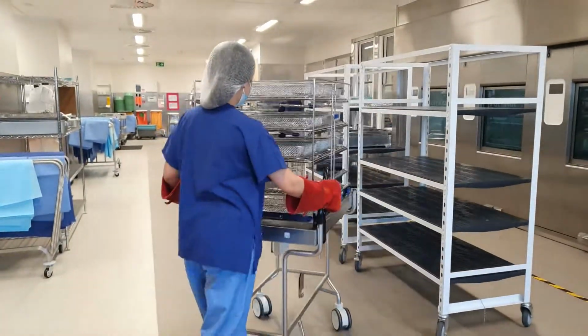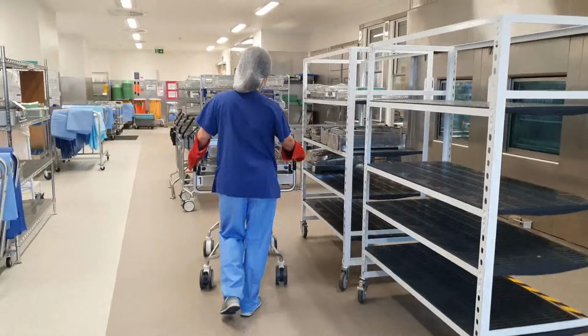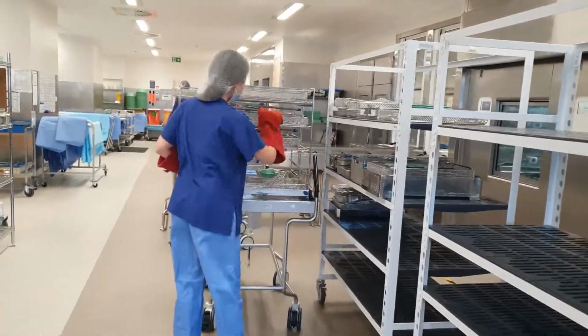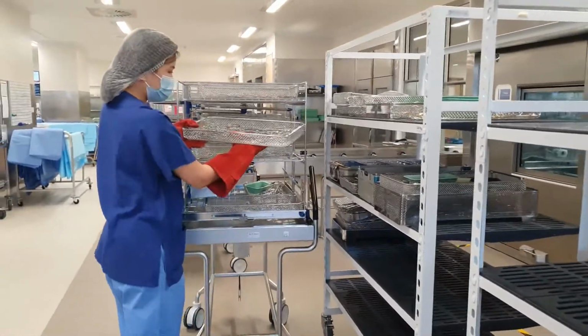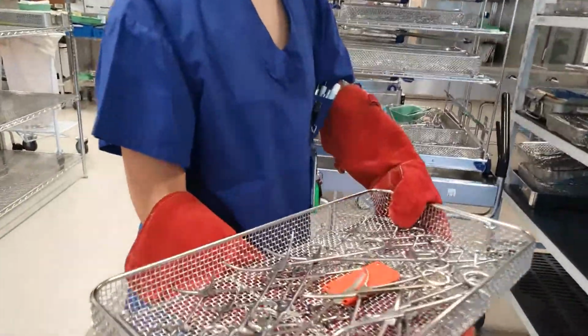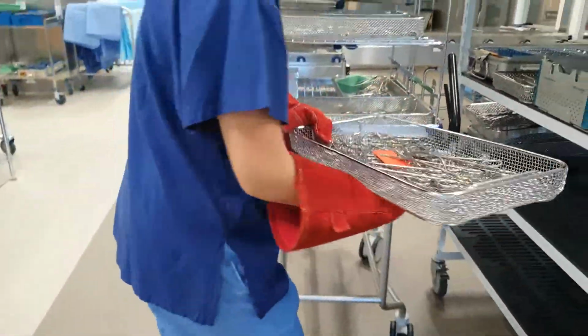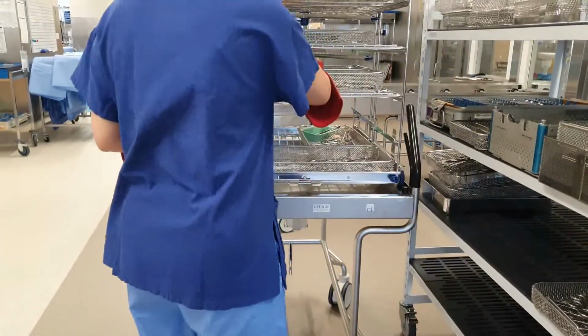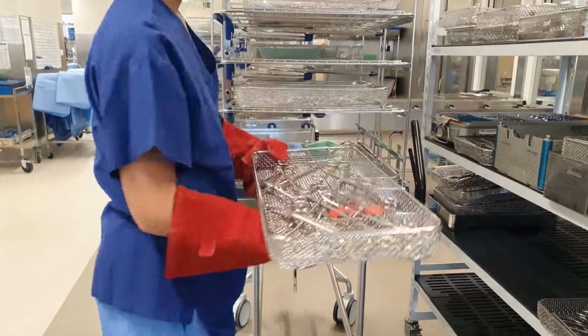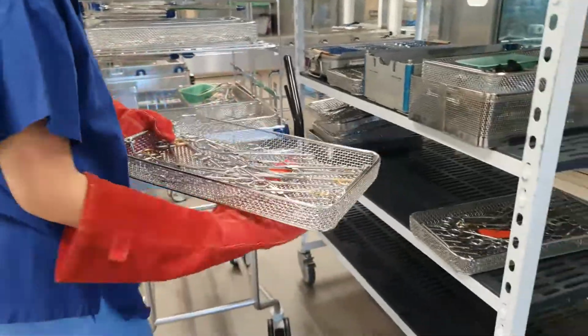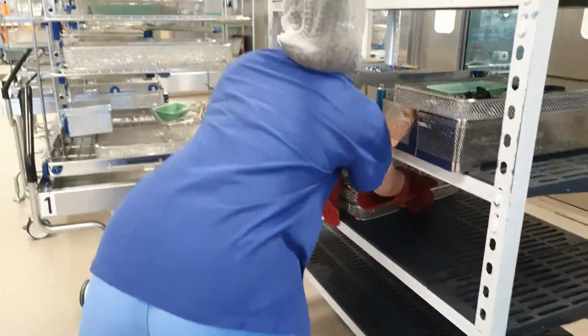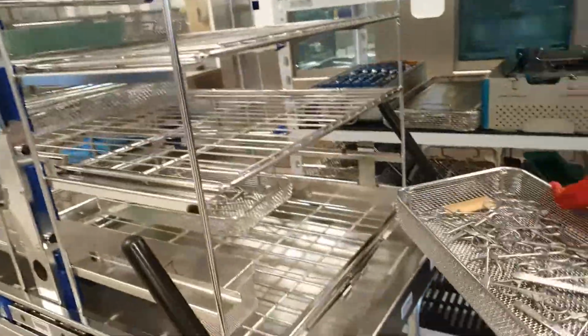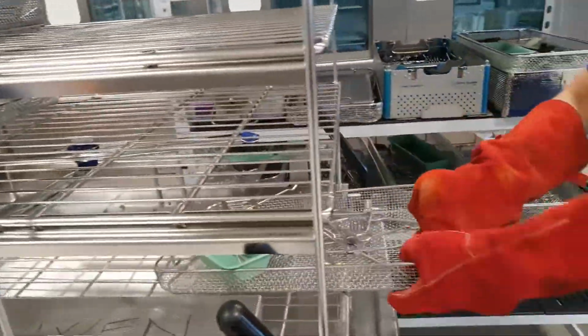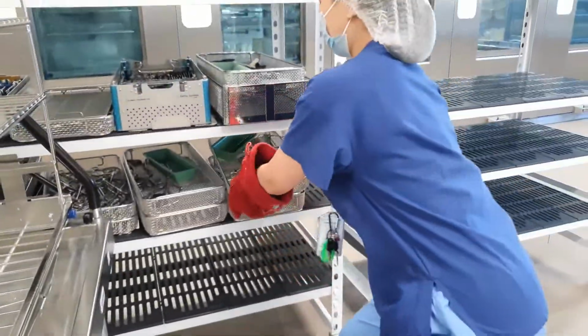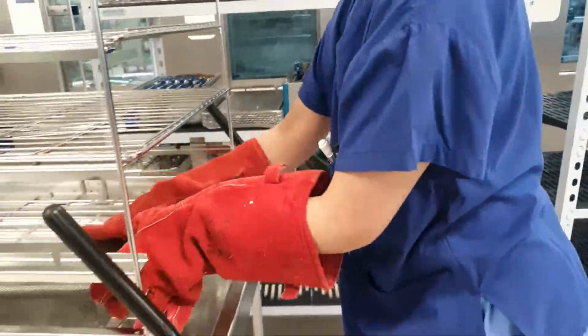After scanning, we unload the instruments and allocate them to their designated areas. Here, I am unloading and putting the trays with the same color tags to keep all instruments that came from one set together. This makes it easier for the person inspecting and keeps a good workflow. Don't forget to wear heat-resistant gloves when unloading, and let the instruments cool down before inspecting or handling them. Remember, when unloading or moving around heavy items, make sure to bend your knees and try to keep your back straight to avoid injuries.